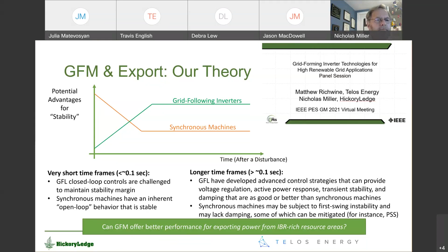We set up a detailed PSCAD model, switching between grid following (GFL), grid forming (GFM), and synchronous machines, all other things being equal, with a very detailed representation of equipment using commercial vendor-based OEM controls, but a single snapshot of them. We played games with the power transfer, the length of the AC lines, and what to do at the midpoint—thousands of cases on a very simple system to try to tease out some basic insights. Next slide.